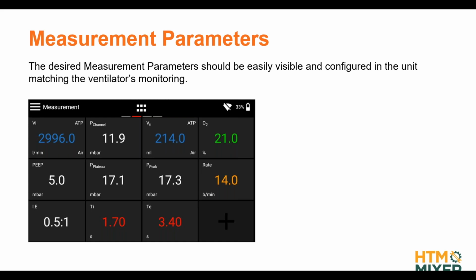The last thing about settings are the measurement parameters. On your gas flow analyzer, you can usually set up your screens exactly how you want. You can configure what you want to see. And here it's important to know that sometimes the terminology is different. For example, one ventilator might use the term frequency for the respiratory rate, while another one, or your gas flow analyzer, may call it rate. Or the maximum pressure during an inspiratory phase may be called P peak on one device, while another device may name it PIP for peak inspiratory pressure. The exact same thing, but different naming.